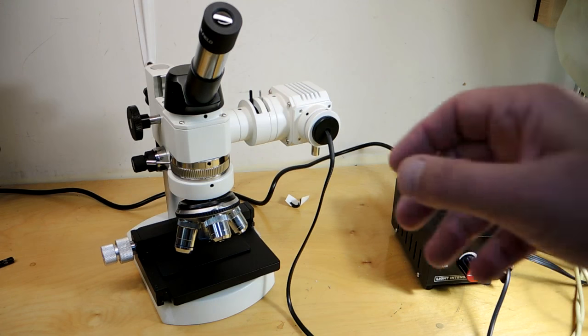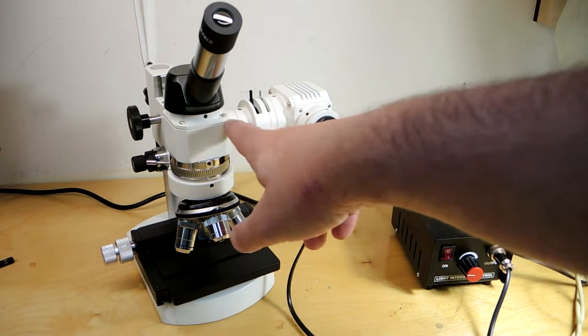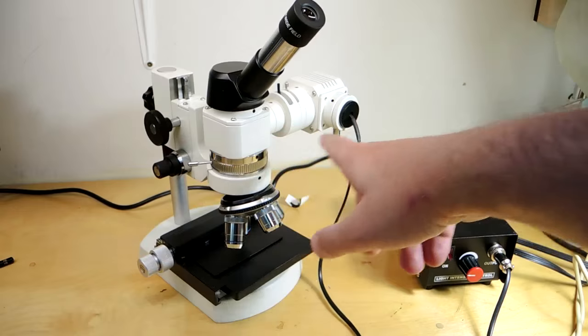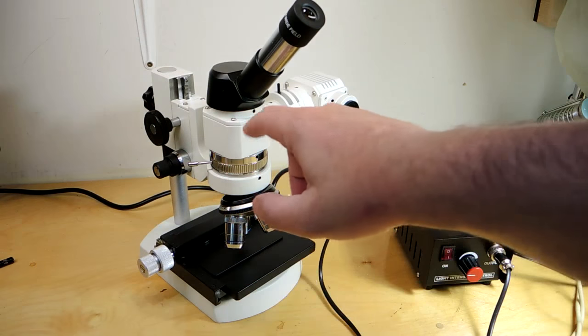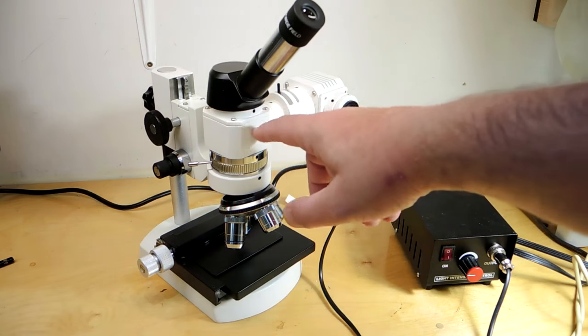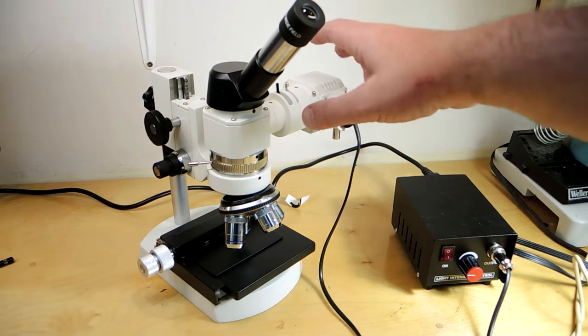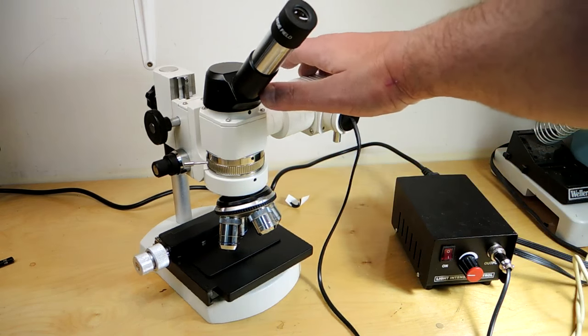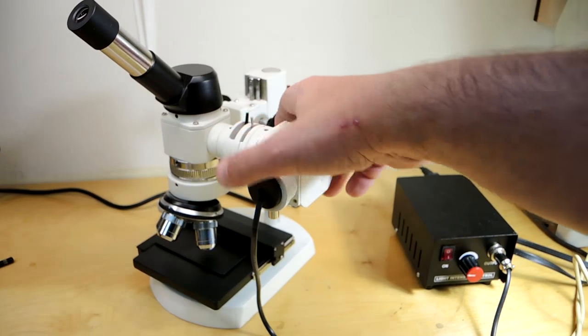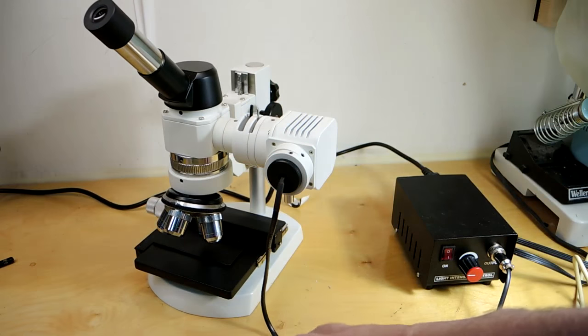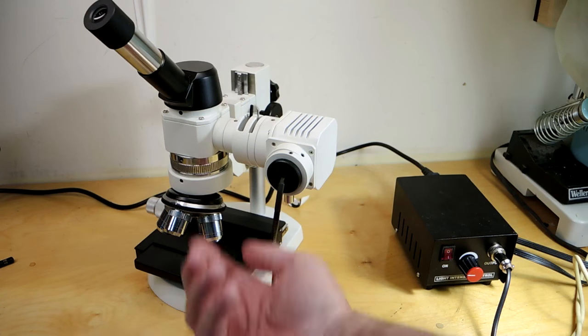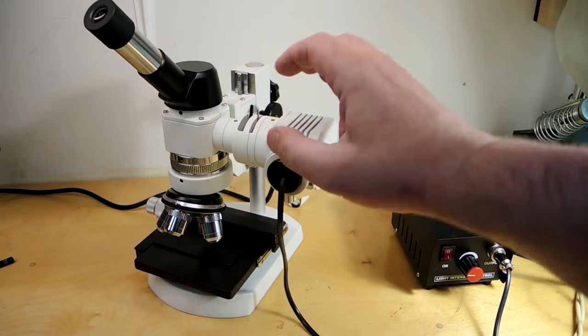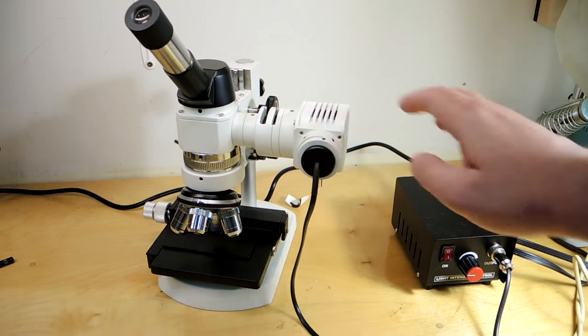If you're not familiar with what a metallurgical microscope is, it has an illuminator on this side here, through the tube. Basically, it pushes light downwards through the tube. There's an interesting construction optically, which allows light to pass one direction and the image to come back the other, and we'll get into that in a minute. When you're looking at metallurgical samples, unlike a traditional microscope where you push light upwards through the sample, you can't do that. So that's what this gadget here is.